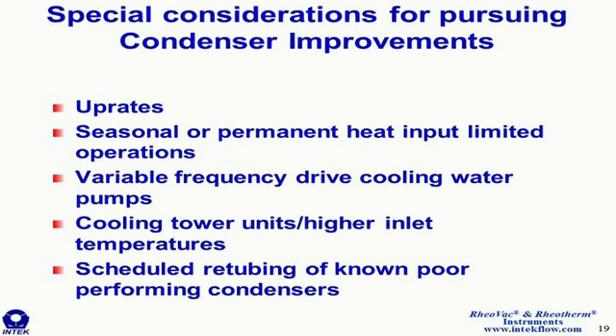The second special consideration is if the unit ever operates with seasonal or permanent heat input limited conditions. Anytime you reduce the condenser pressure through an upgrade, you're able to generate more megawatts, and the payback period drops from something like 2 to 3 years to under a year. If the unit has variable frequency drive cooling water pumps, then you can save station power by throttling back on your cooling water pump power and deliver more to the grid. Reducing the condenser pressure gives you that flexibility to throttle back on your cooling water usage.